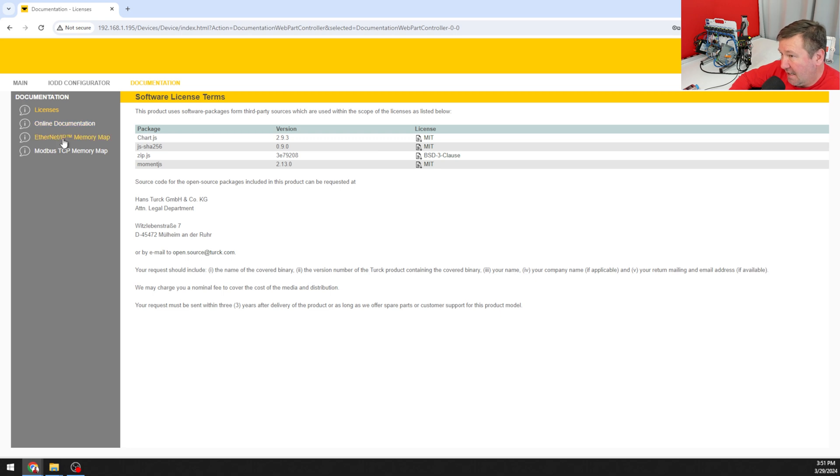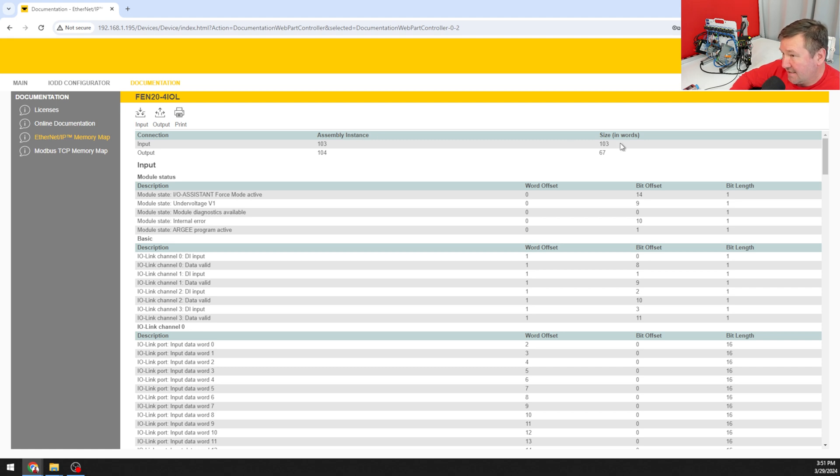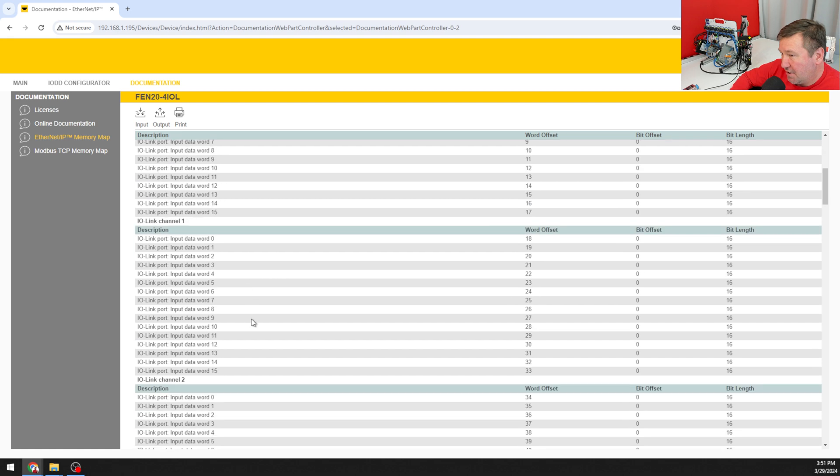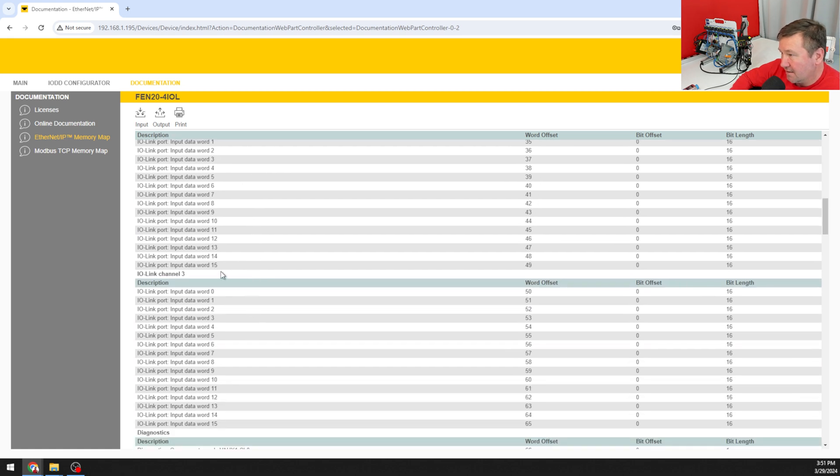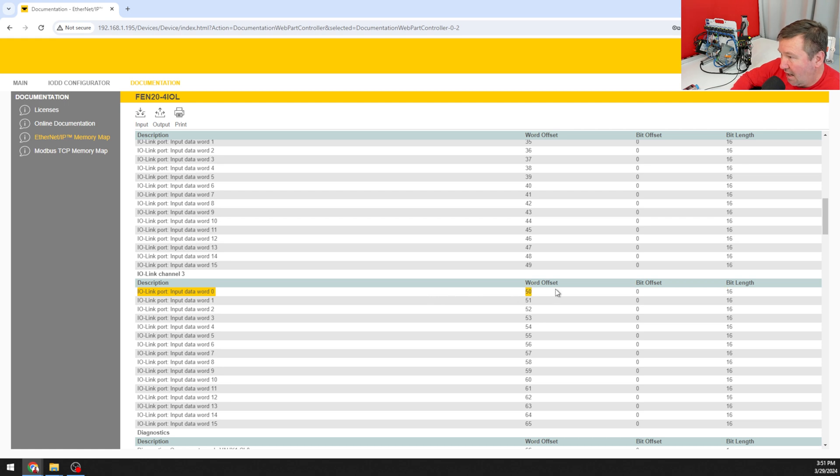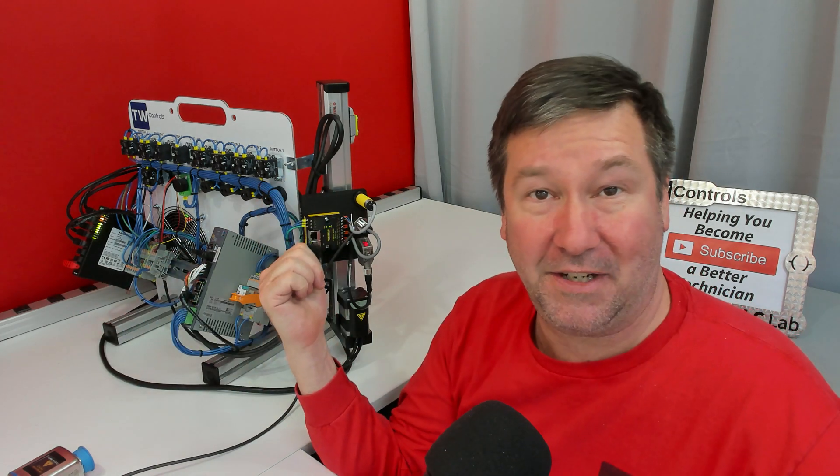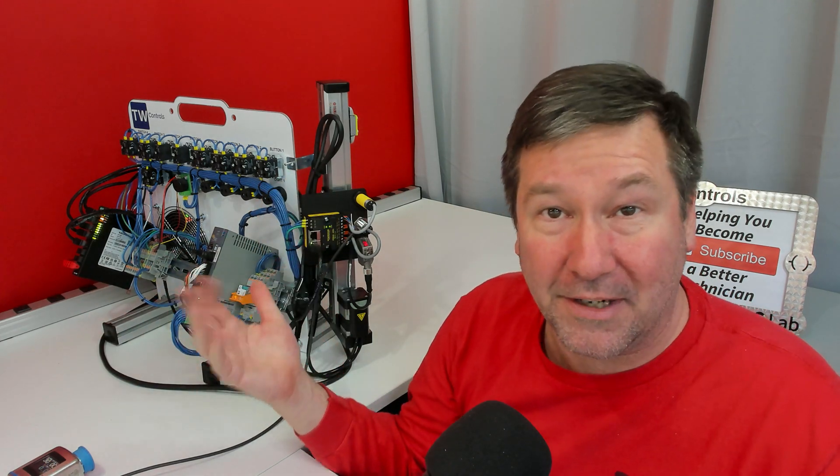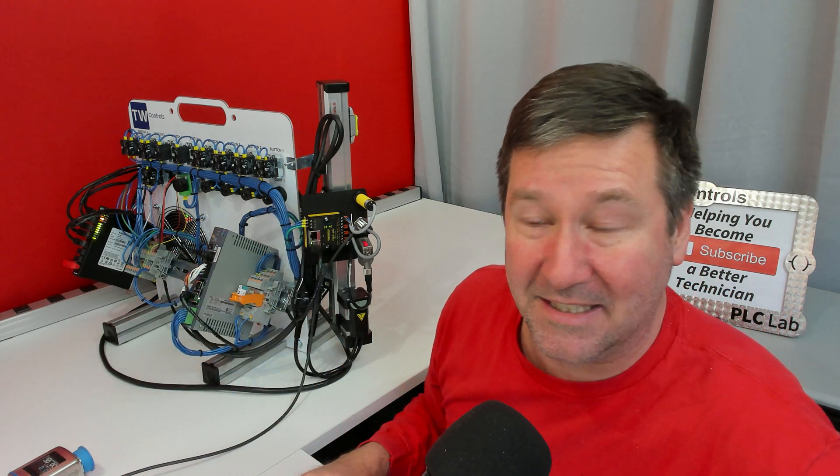We can see our assembly instance and size and if we go down here we can see where channel 3 is going to start. Our data is going to start coming across at word offset 50. And we have videos on how to configure this over ethernet IP and Modbus TCP.